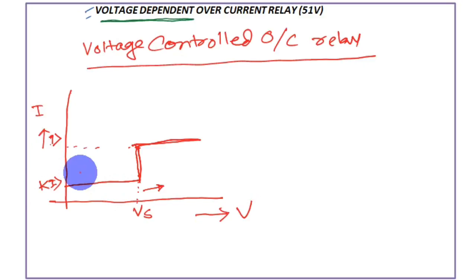When a fault happens away from the generator, the voltage at the generator terminal will not fall, so it acts as a normal overcurrent protection with a higher pickup current. But if the fault is near the generator, the terminal voltage falls below Vs, reducing the pickup current to Ki. This lower pickup current triggers the relay to operate faster. That is the operating principle of the voltage controlled overcurrent relay.